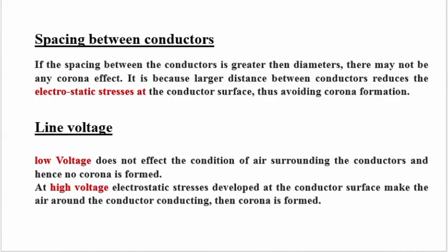But if we apply high voltages, then high electrostatic stress will develop around the conductor, which will ionize the air surrounding the conductor, and as a result corona will be formed. But remember, when there is moisture or humidity in the air surrounding the conductor, then corona formation can also occur even at low voltages.